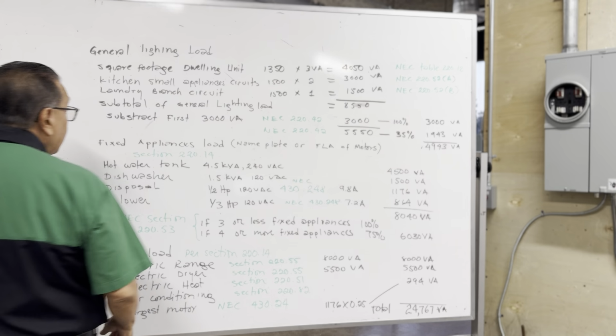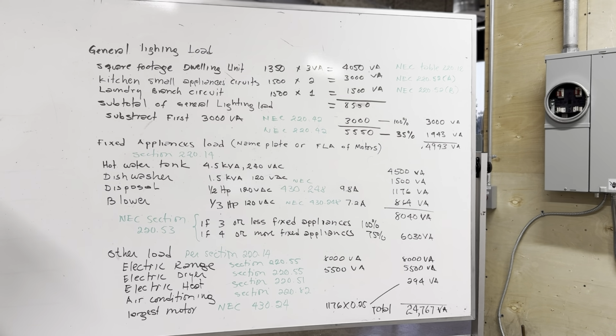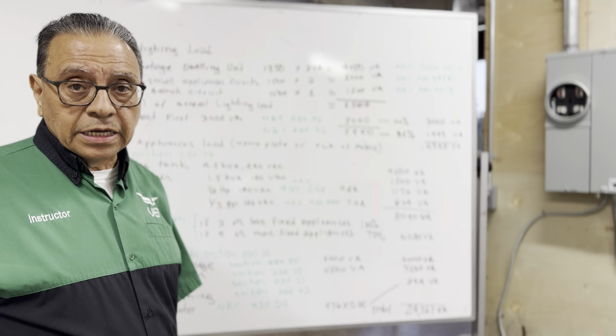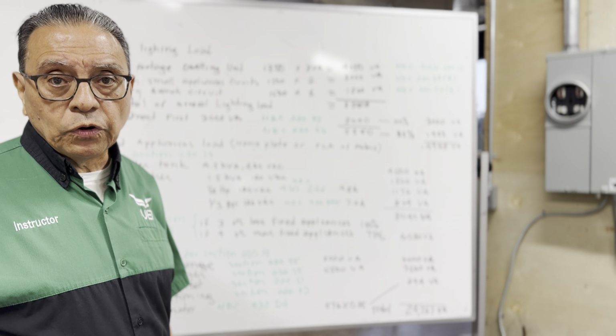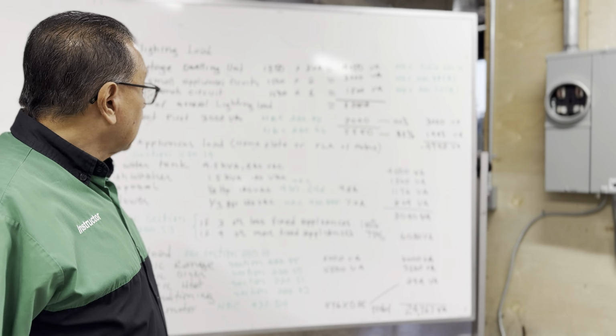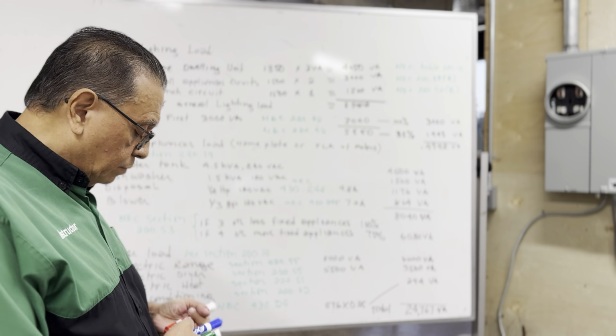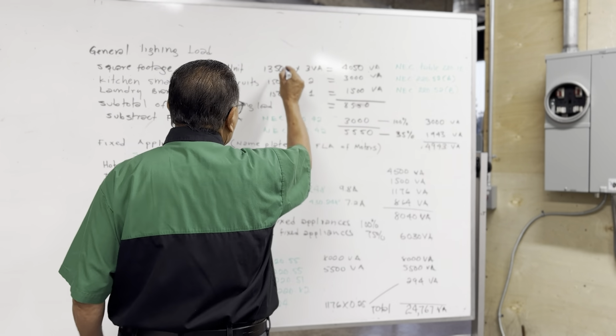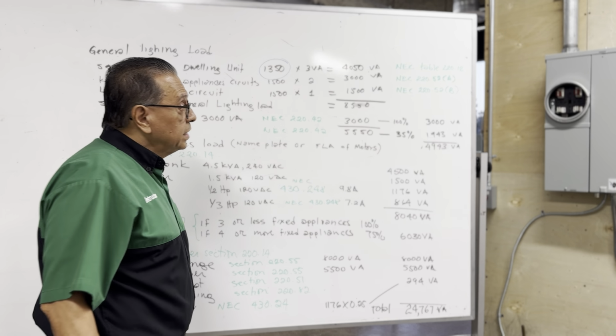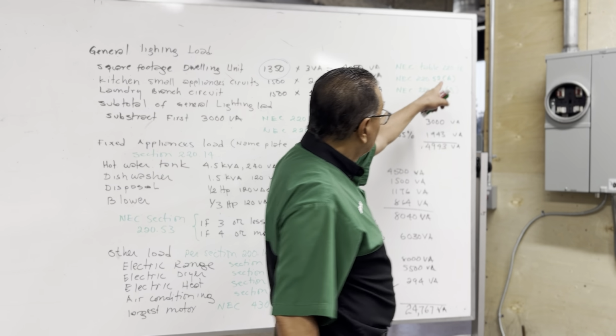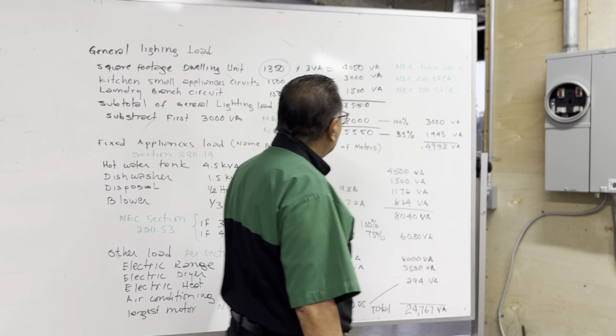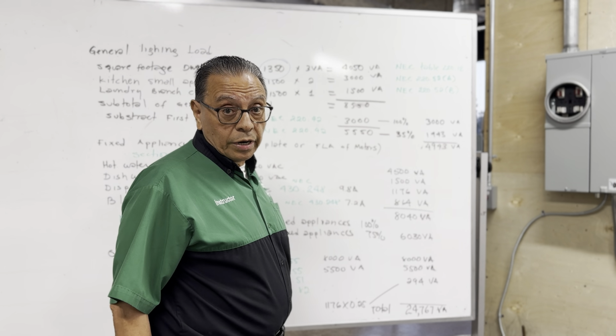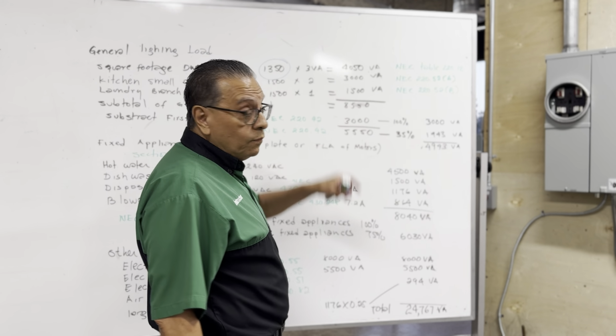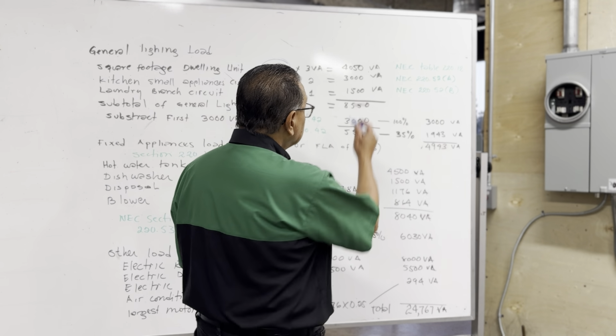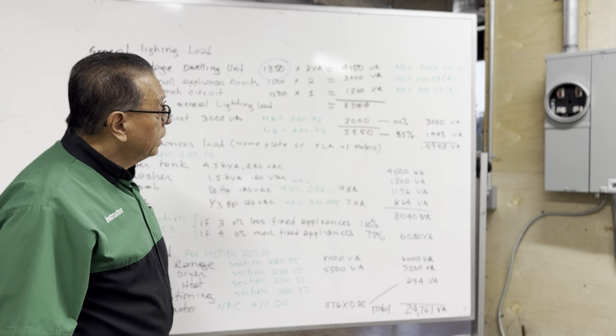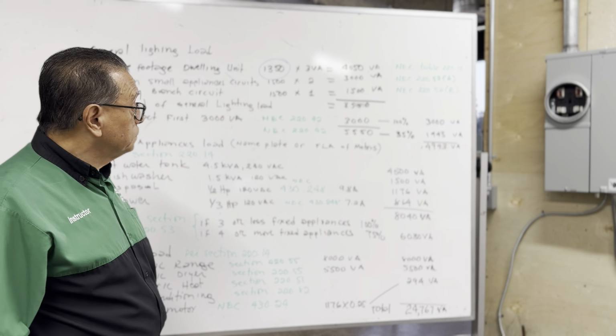Okay, right here, what we have is, as I told you, a dwelling unit whose total square footage is 1,350. Okay, that is my... and according to NEC table 220.12, I need to multiply the total square feet times 3 volt ampere. And in this case, I am getting 4,050 volt ampere.